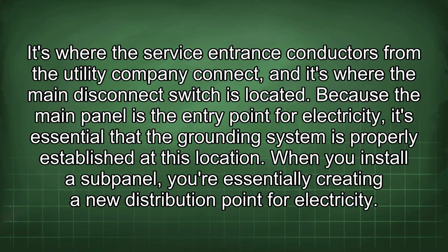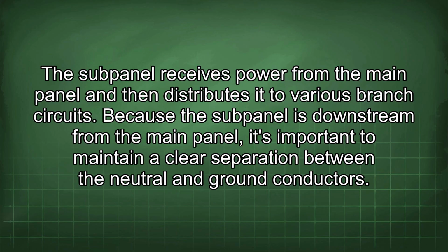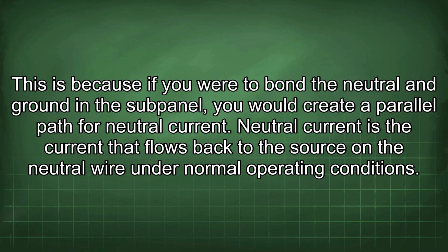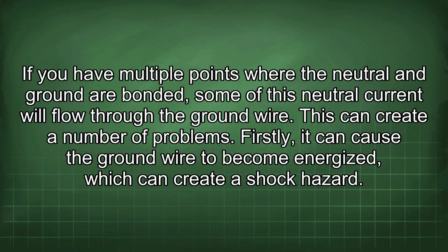When you install a subpanel, you're essentially creating a new distribution point for electricity. The subpanel receives power from the main panel and then distributes it to various branch circuits. Because the subpanel is downstream from the main panel, it's important to maintain a clear separation between the neutral and ground conductors. This is because if you were to bond the neutral and ground in the subpanel, you would create a parallel path for neutral current. Neutral current is the current that flows back to the source on the neutral wire under normal operating conditions. If you have multiple points where the neutral and ground are bonded, some of this neutral current will flow through the ground wire. This can create a number of problems.